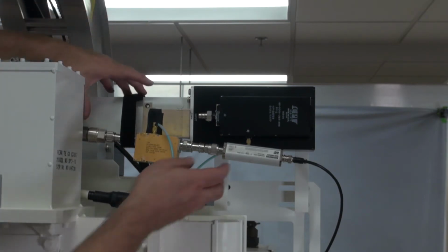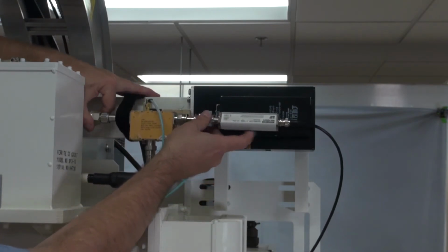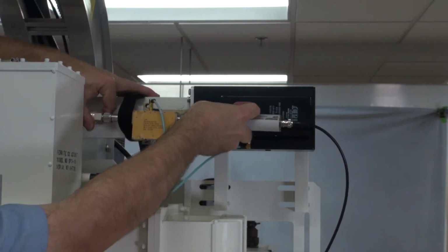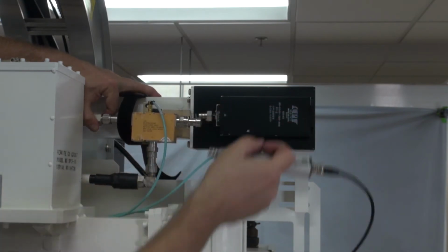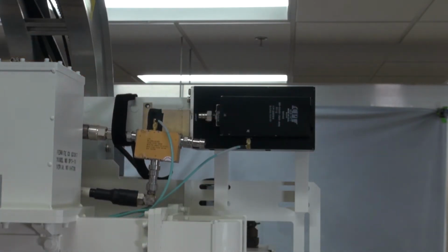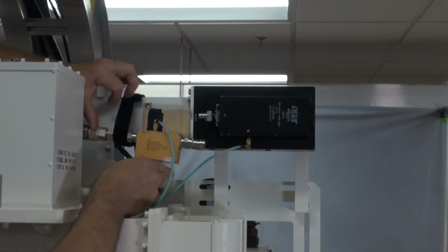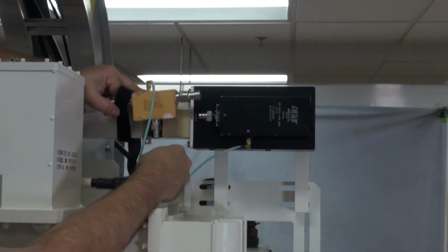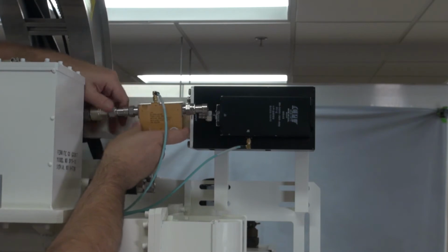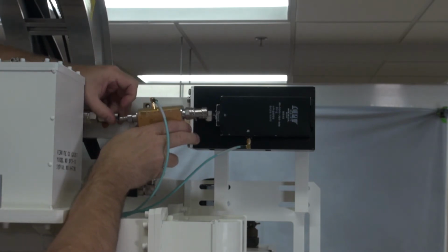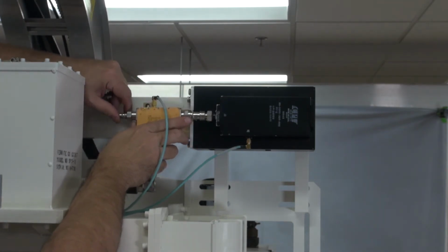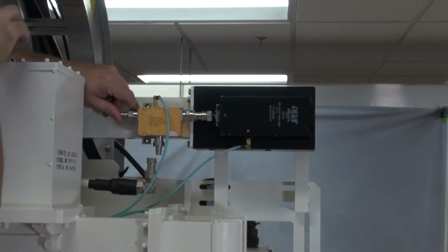Again, the sequence of the following procedures reduces the risk of damage to the LNA. Disconnect the test equipment from the LNA. Reconnect horizontal LNA to the TR limiter as follows. Disconnect cable 2W556 and 2W577 from the LNA. Connect the LNA to the TR limiter.